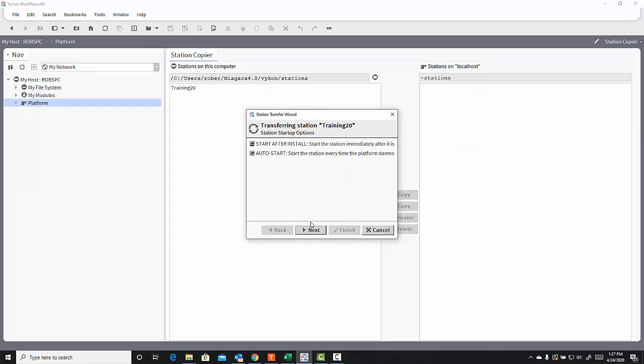When we get to the Station Copier, the Station Transfer Wizard appears, and I can choose to have this start immediately after installation, which I will leave it set to do. And I can also choose to have this station auto-start, so that when Windows boots up, the station begins to run as soon as possible. Now, for a supervisor station, one that I was building for a customer site to act as a supervisor to other stations, I would leave that auto-start check mark checked.